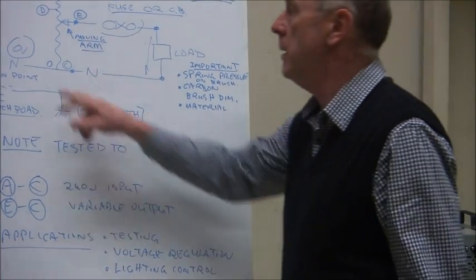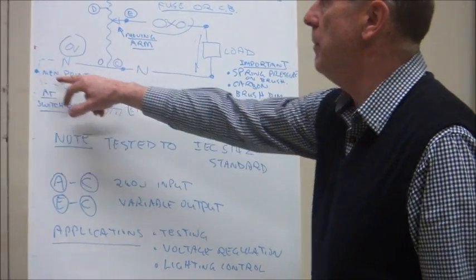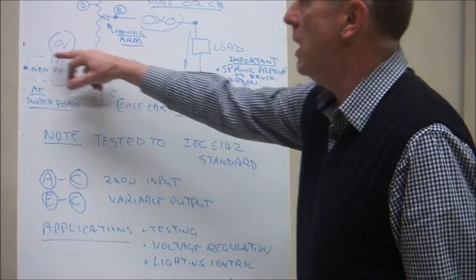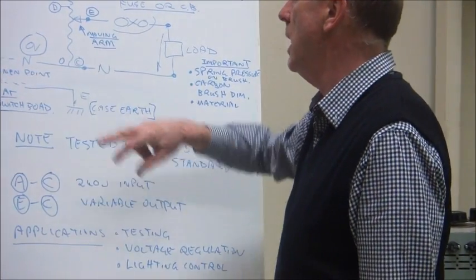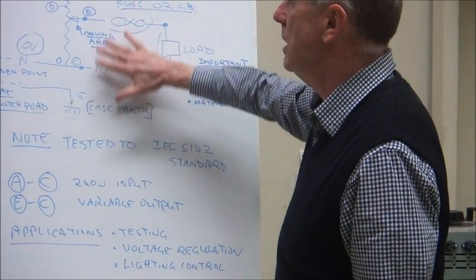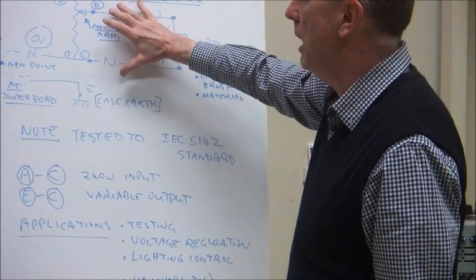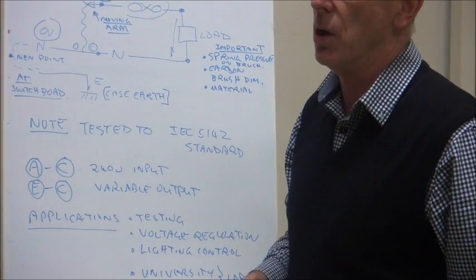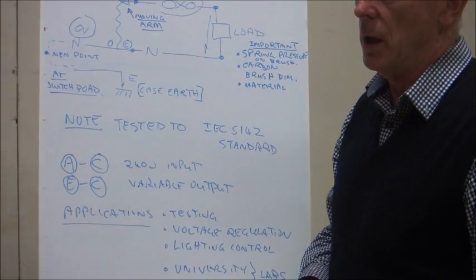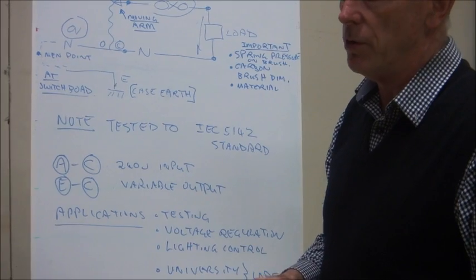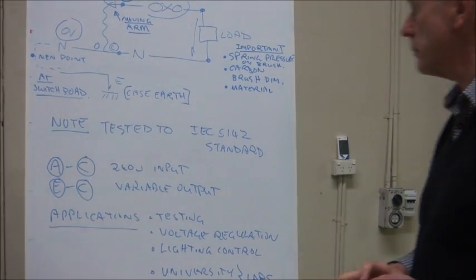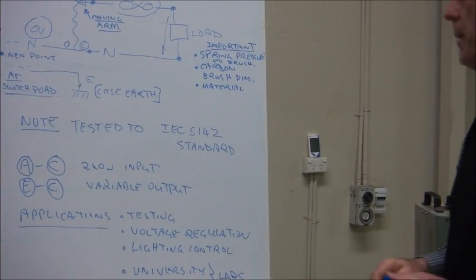An MEN, the neutral and the earth are connected back at the switchboard, so you have an MEN connection. That means you can use a residual current device or an earth leakage circuit breaker here on the output side to protect you against electric shock. And that's something that in a TAFE or in a laboratory would be recommended. So that's about it.